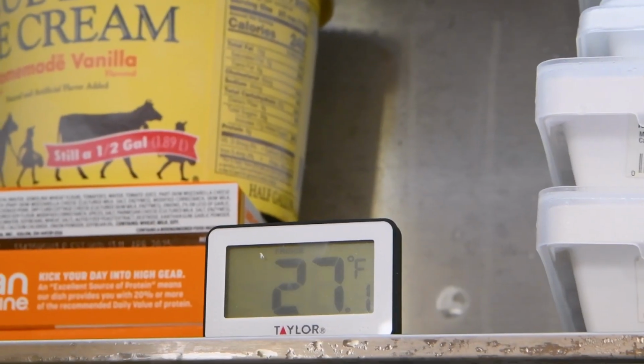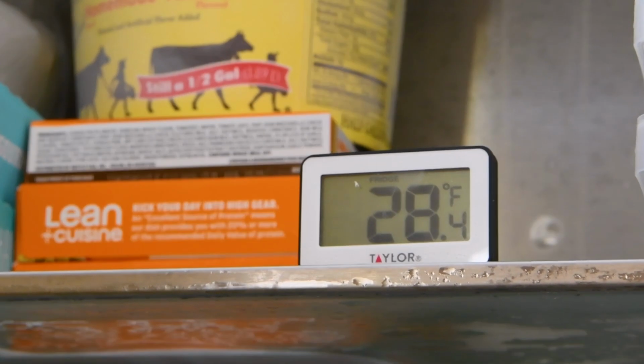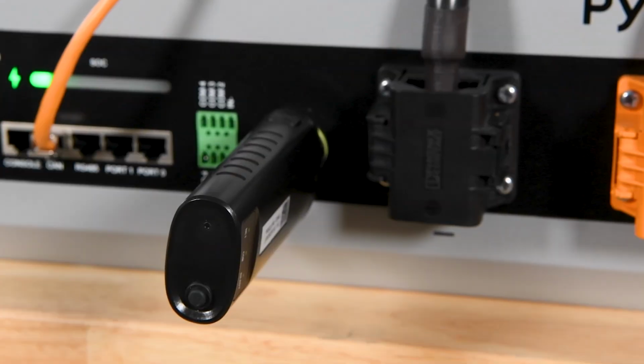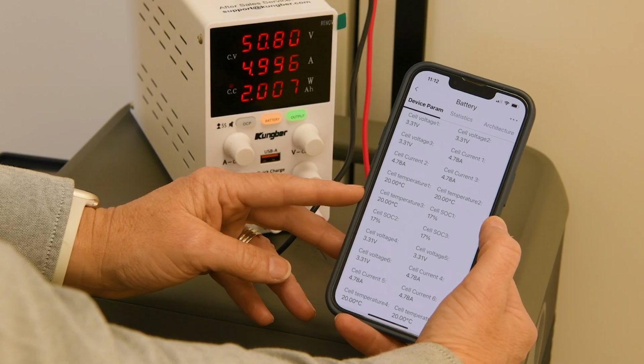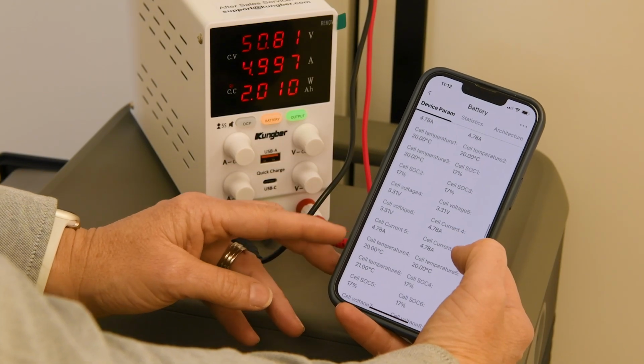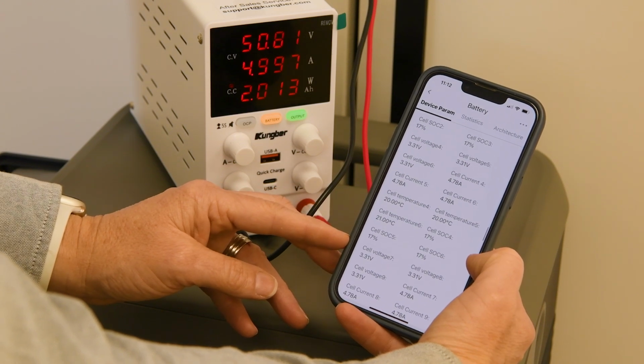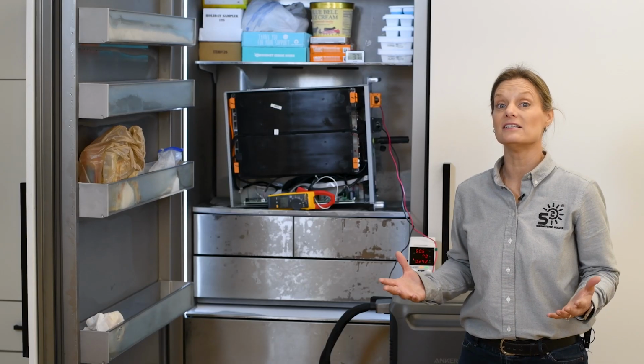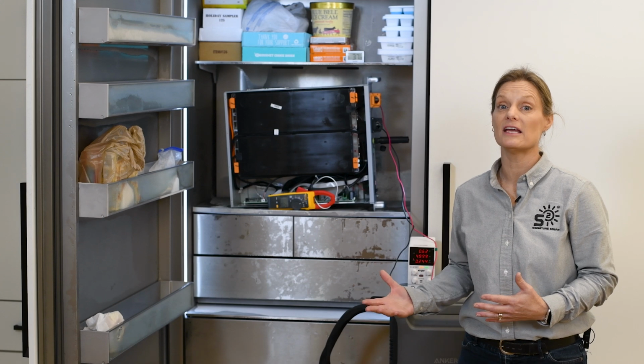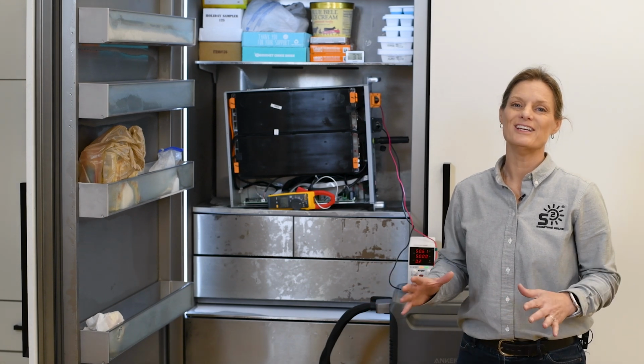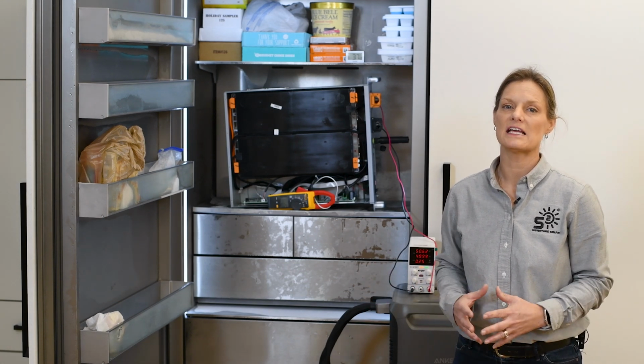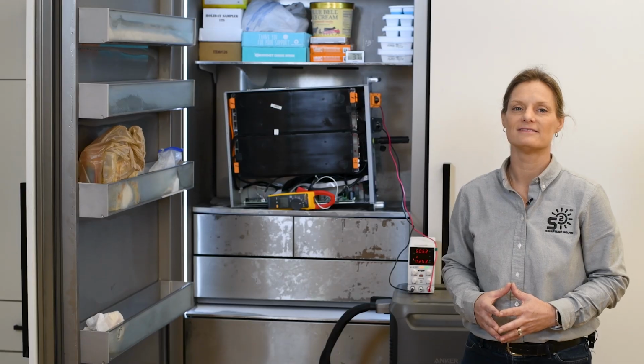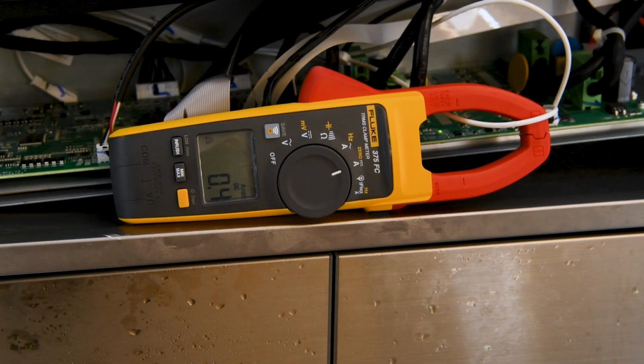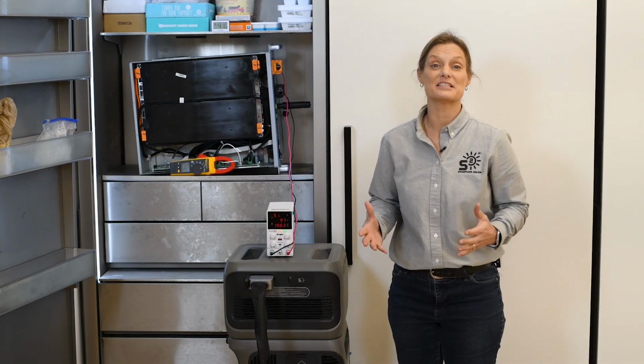We're monitoring the ambient temperature with this thermometer inside the freezer, and we'll use the Pytes Wi-Fi dongle to record the battery cell's internal temperature, giving us a real-time view of when the heating pad kicks in. Ideally, we'll see the heating pad activate when the temperature dips low, ensuring the battery stays within a safe range for charging. There it is, our clamp meter is now reading current flow, indicating the heating pad has activated as expected.